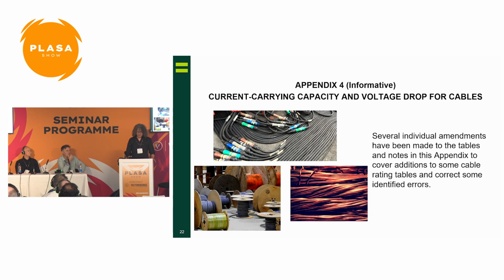So what's next? This is one of the last points I want to bring out - a change to Appendix 4. Appendix 4 is about the current carrying capacities of cables and volt drop, that kind of thing. What's being added is that if you've got cable in ducts, the permitted currents for cables in ducts are different to other types of installations, like buried cables, for example.